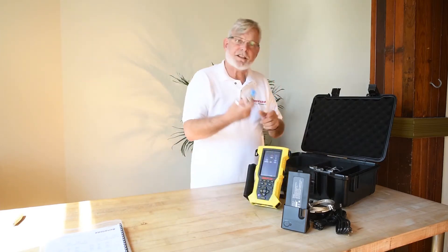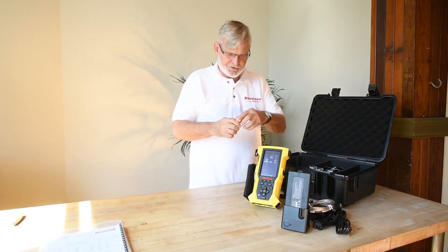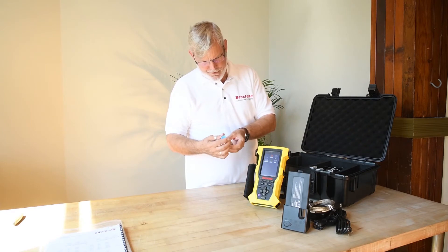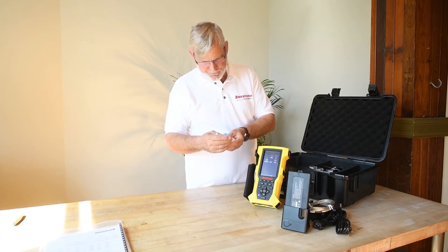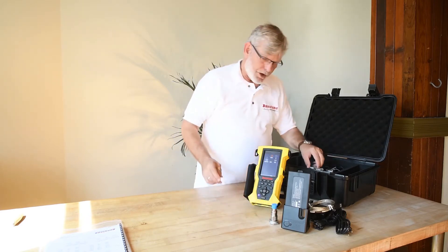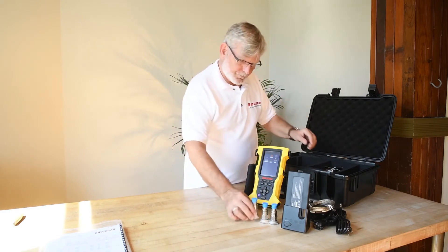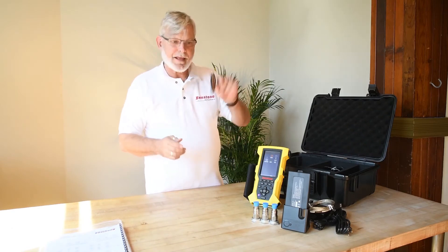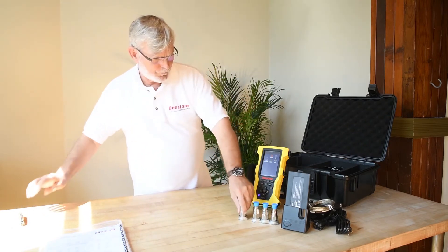Four sensors, as per the calibration certificates. They have magnets on them, and they are Benstone Instruments model 786A, 100 millivolts per G. And there's one, two, three, four.